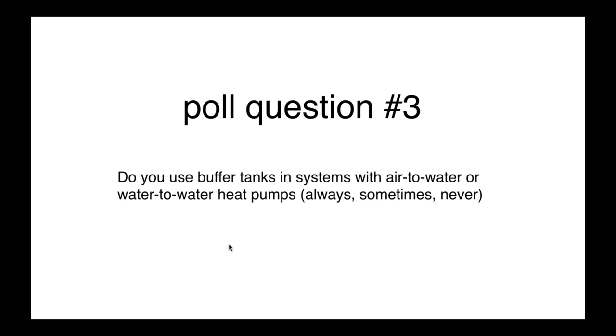You still want hydraulic separation between the heat pump and the balance of the system. But as long as you can match the load with the output of the heat pump, we've got the balance we need. Once you start to get into what we call micro zoning or micro loading, if, for example, you tell me I want a panel radiator in each room or a separate radiant ceiling panel in each room with TRVs on it or thermostats, I'm going to tell you to put a buffer tank in regardless of the heat pump, because you're easily creating loads that are a small fraction of even the lowest capacity of a modulating heat pump. Okay, let me just move that and we will go on.